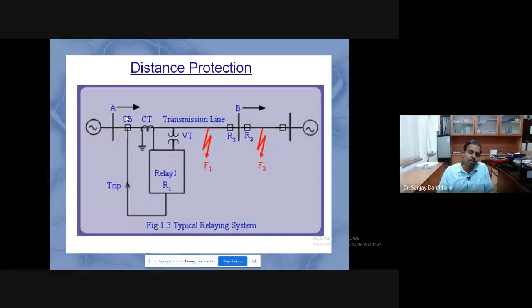Right. So this is distance protection, which basically takes the current and voltage information, computes the impedance, and then if the impedance is beyond the set value, then you can say that there is no fault. But in case of fault, suppose the fault is at F1, the impedance computed by this distance relay falls below the transmission line impedance, and that can be treated as a fault, and the trip signal to the circuit breaker can be generated, and the circuit breaker can be asked to trip.